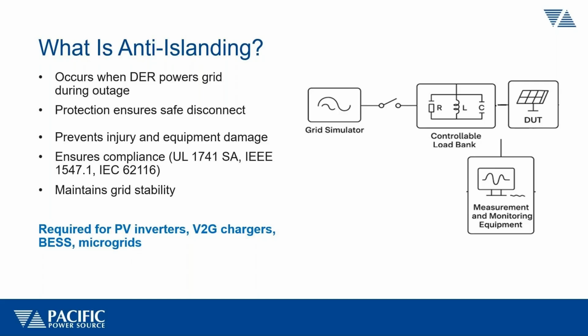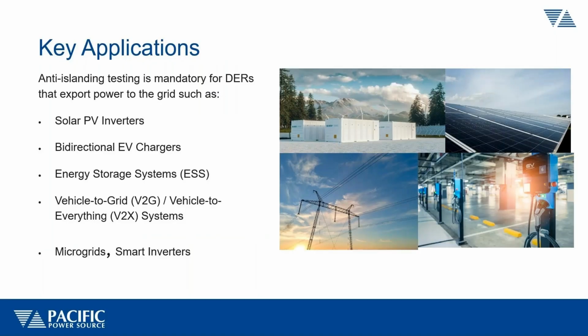So if we look at some key applications for this, we'll go into a little more detail on that test setup next. But it's a mandatory requirement for distributed energy resources. So it's not an option. You have to do a type test on any inverter model, and it has to be certified. And it's not something you can typically do yourself unless you're a large company with the resources to do it. So most manufacturers will go to a third-party lab like UL or any other recognized test lab that is certified to do these tests.